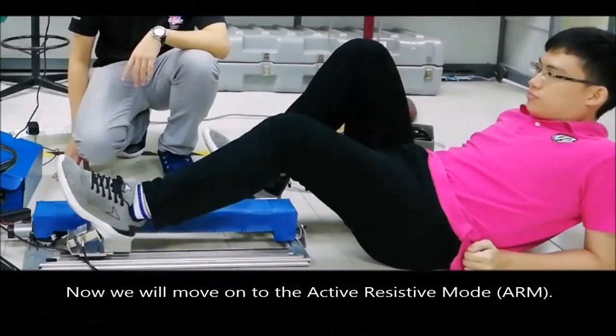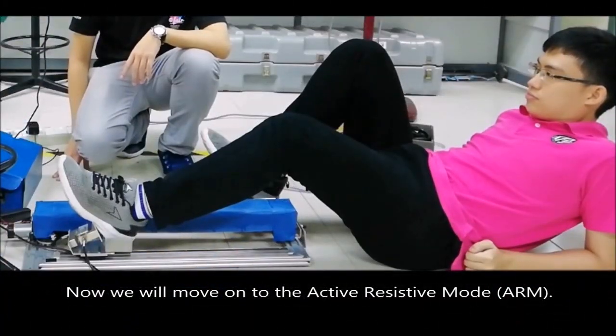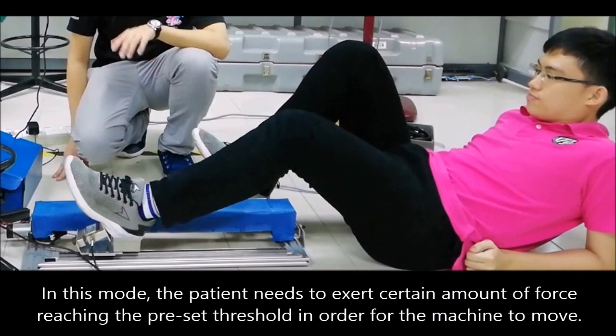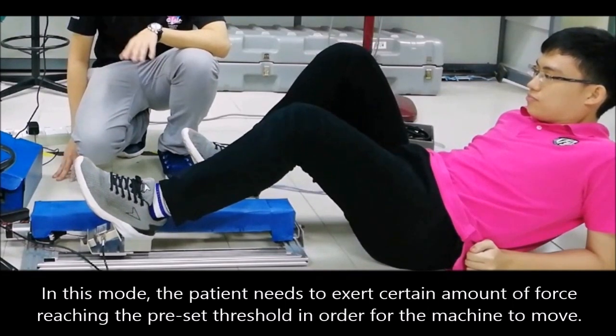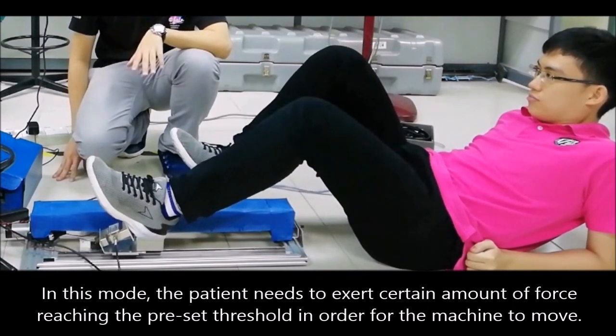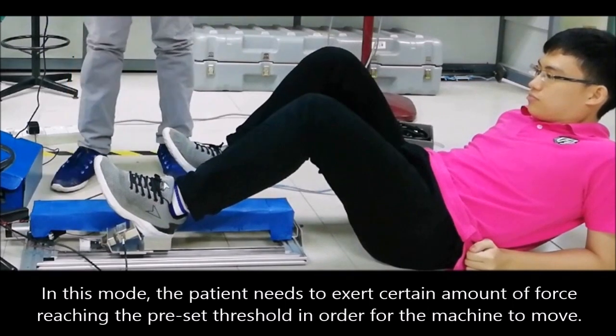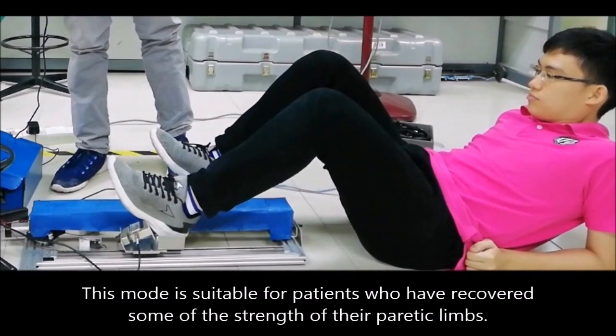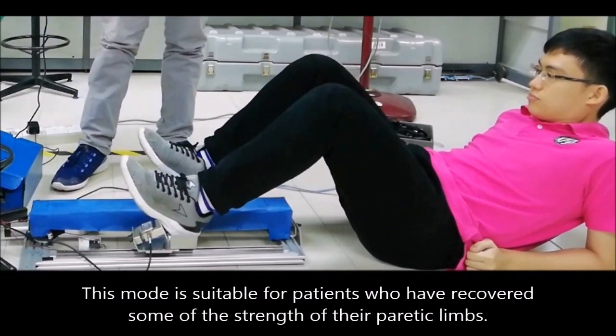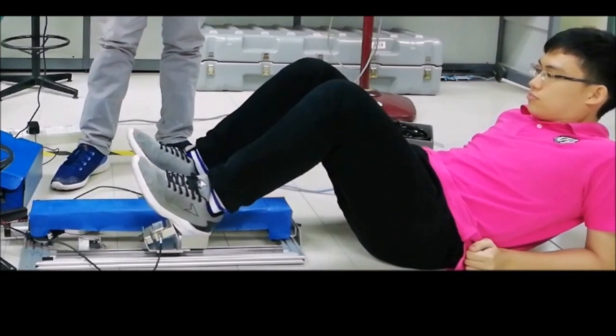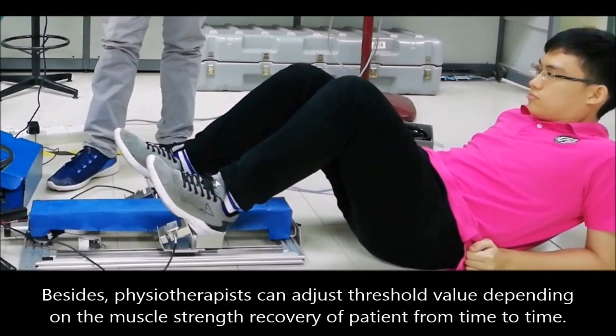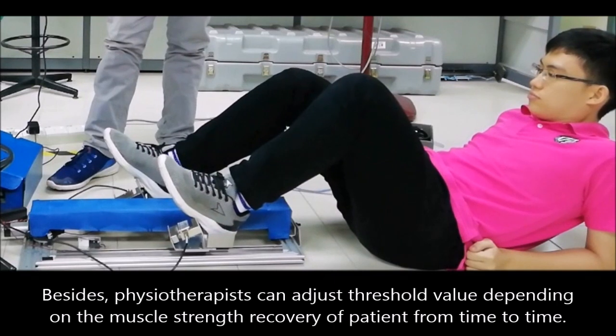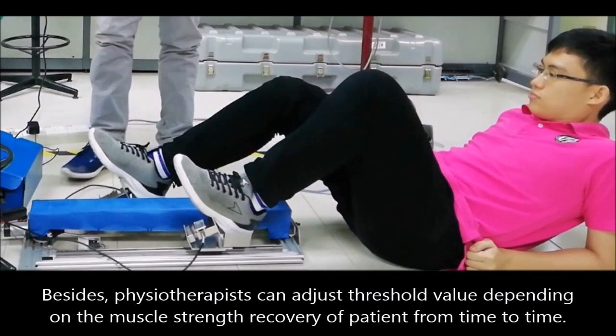Now we will move on to the active resistive mode, ARM. In this mode, the patient needs to exert certain amount of force reaching the preset threshold in order for the machine to move. This mode is suitable for patients who have recovered some of the strength of their paretic limbs. Besides, physiotherapists can adjust the threshold value depending on the muscle strength recovery of patient from time to time.